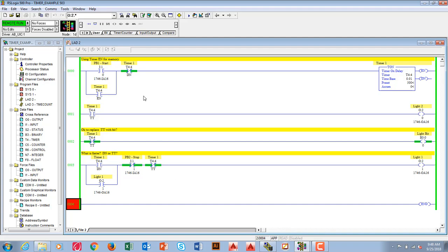So let's see that. I'm going to hit the switch again up there. It's timing. Because it's timing, this becomes false. And then it returned to the true state. And now my light is on, which means that this done bit right here came on for the briefest of seconds. So this timer right here was timing. It got done, and it executed the done on these rungs here.